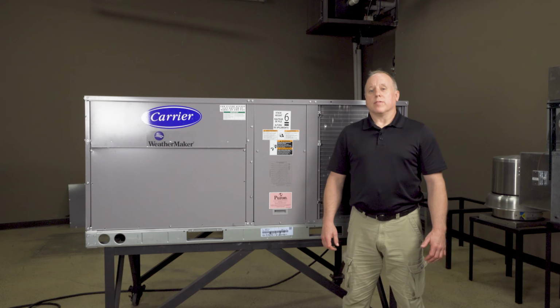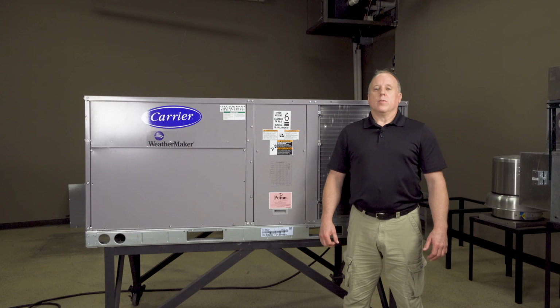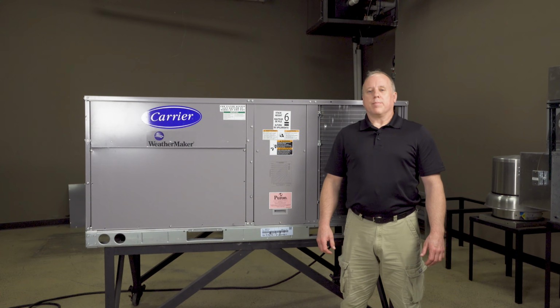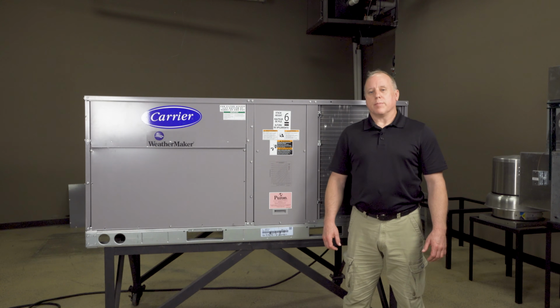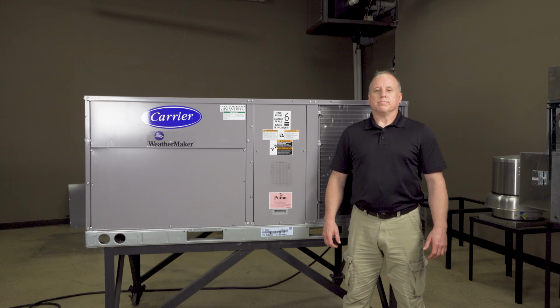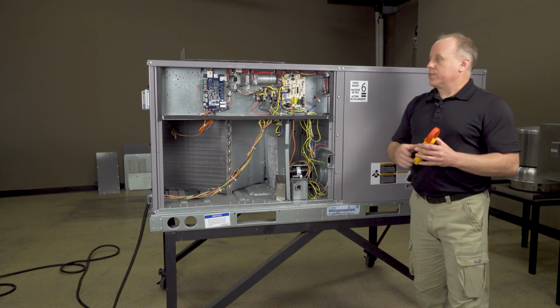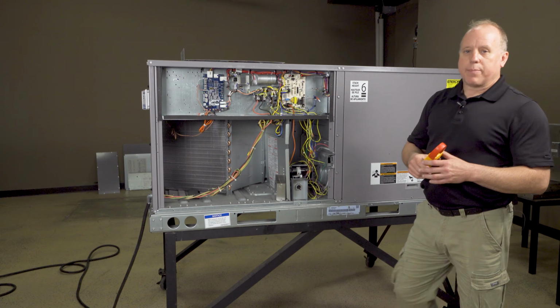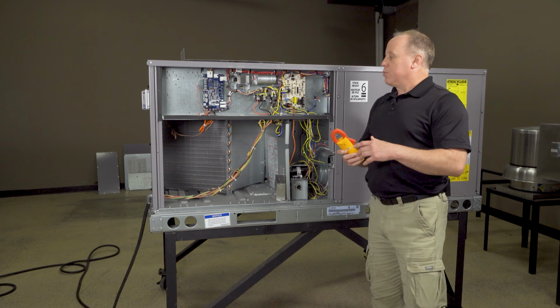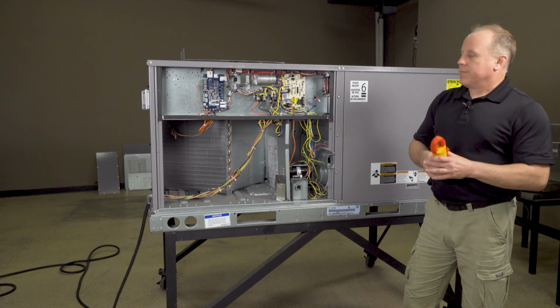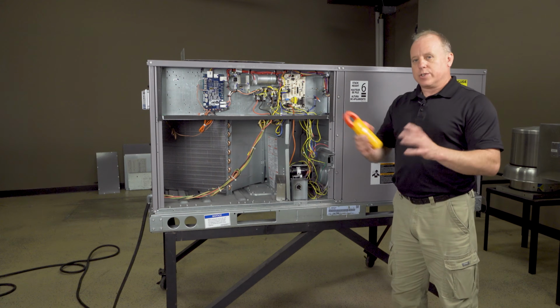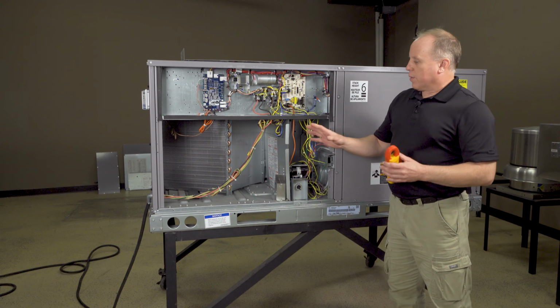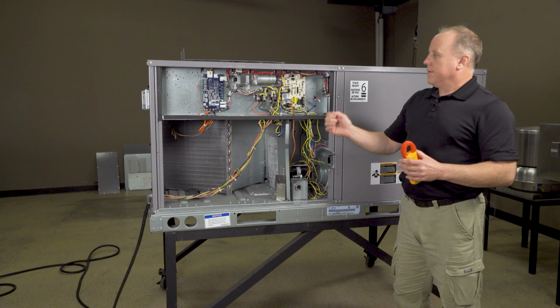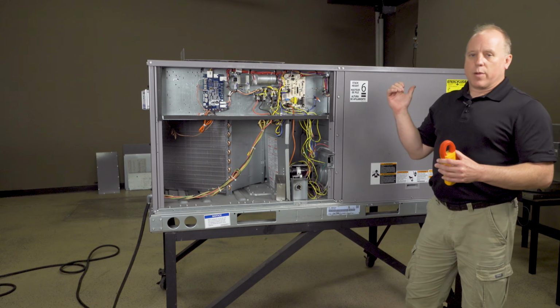Today we're going to be going over some rooftop maintenance. We'll be going over the cleaning of the unit and getting some basic readings and numbers to make sure your unit's operating properly. Now we're going to go over checking some numbers on the unit while it's operating. We're going to be checking amp draws on a few items just to make sure the unit's running in the range that it should be. Things we're going to be looking at: compressor, condenser fan, and our blower.